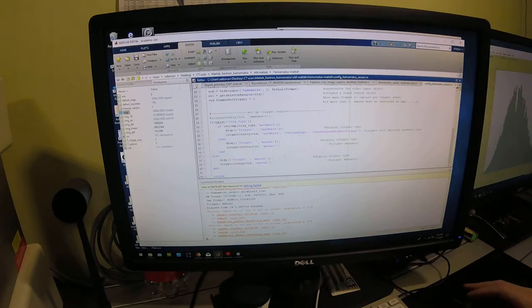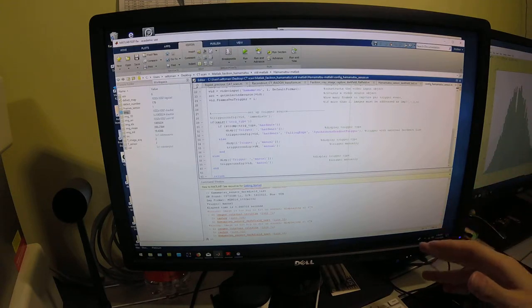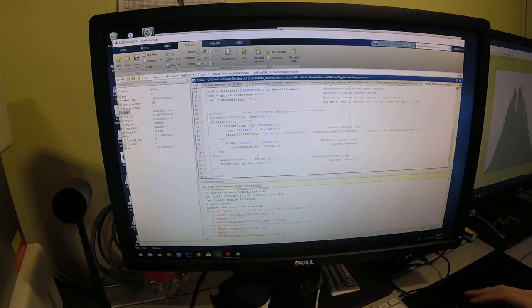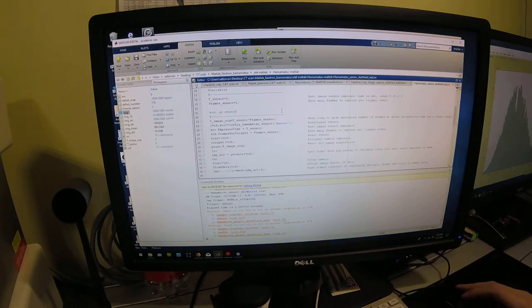And the Hamamatsu flat panel detectors do have a hardware trigger line, so they have a port on the side which, if you pull low, it will generate a trigger and start image integration. However, for this system, we'll be using the manual trigger, which requires a manual function call. So this script will test the dark field capture of the sensor.